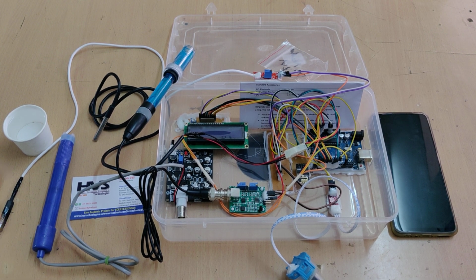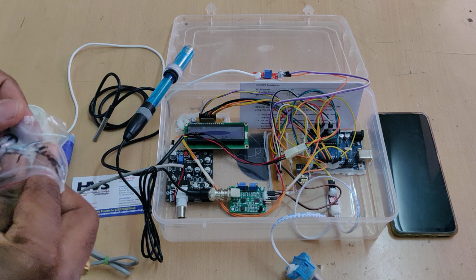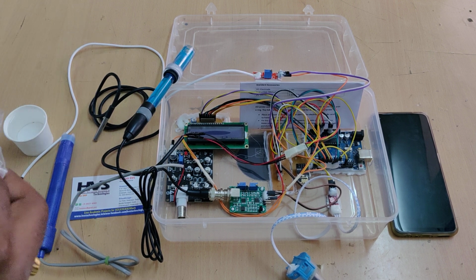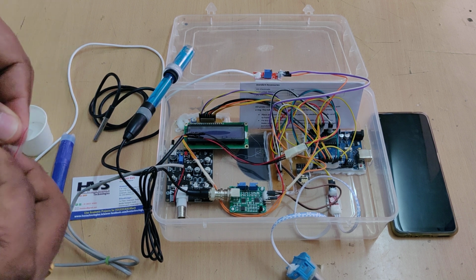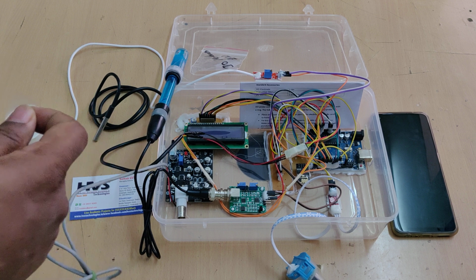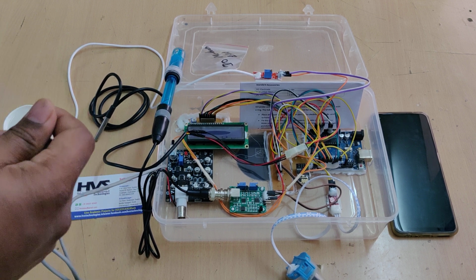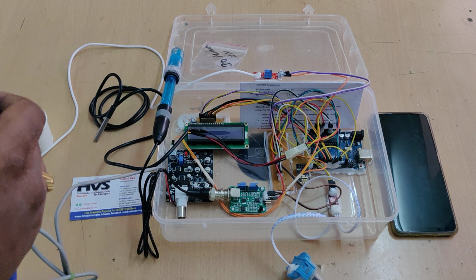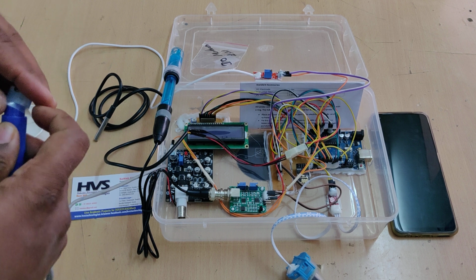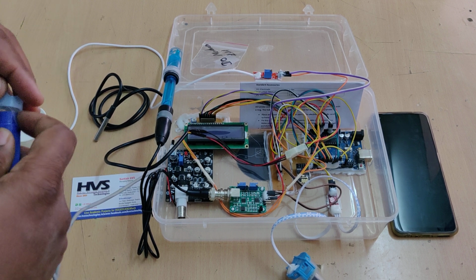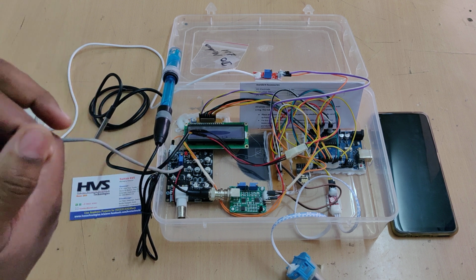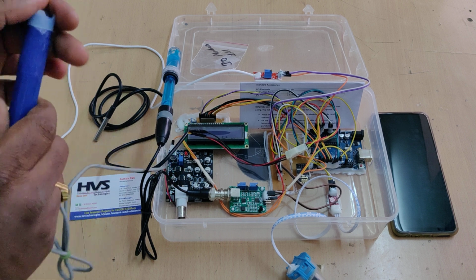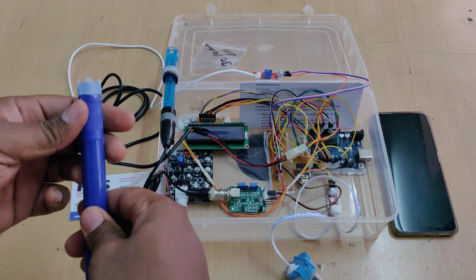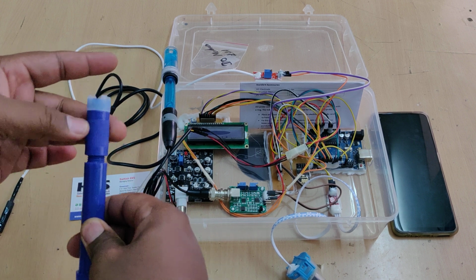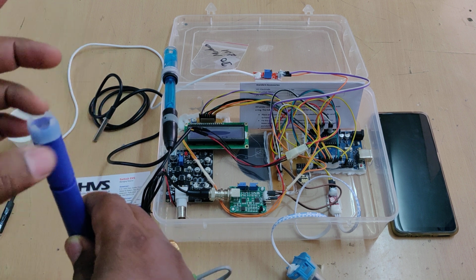Coming to the DO sensor, before the demonstration, that is before dipping the DO sensor inside the water, these membrane sheets should be inserted properly. Take a sheet and remove this white cap. We need to close this without any bubbles. Now close that, properly and very gently. Inside this there will be silver electrodes, so we can see that. There are silver electrodes along with the copper.